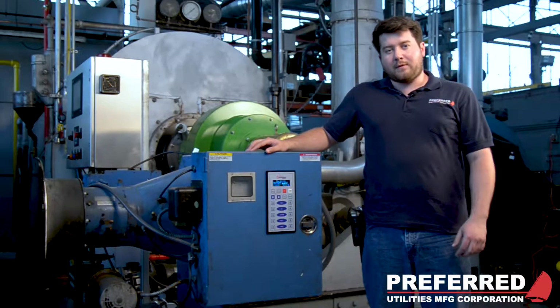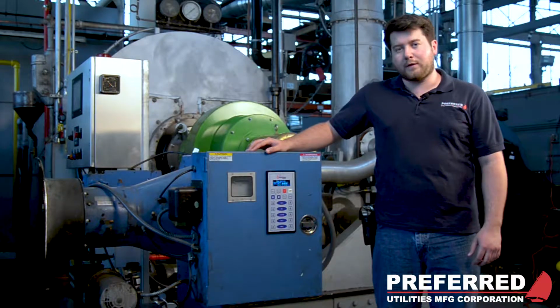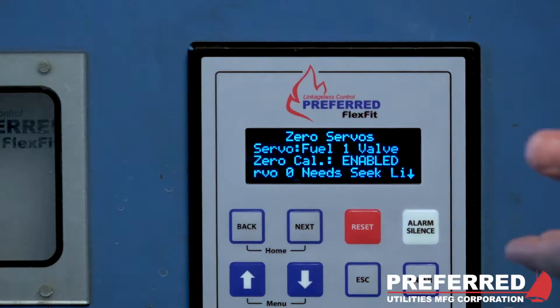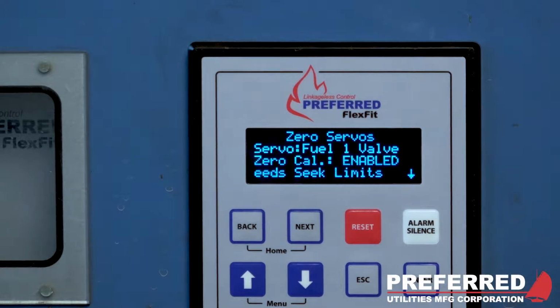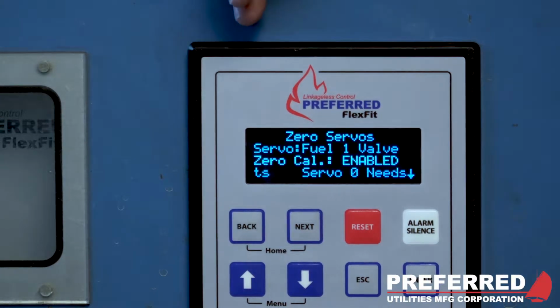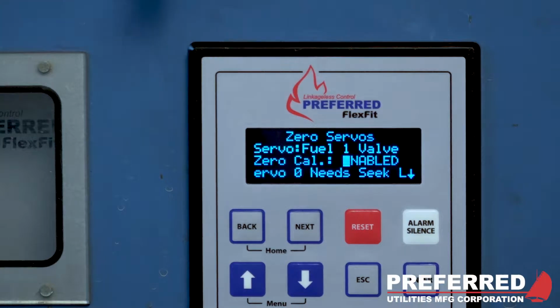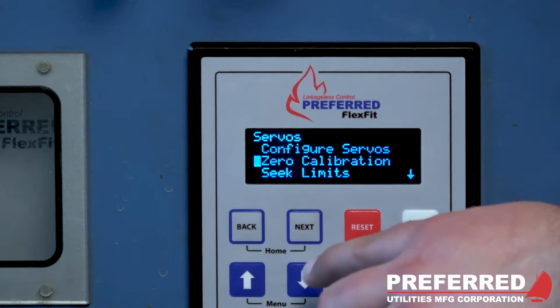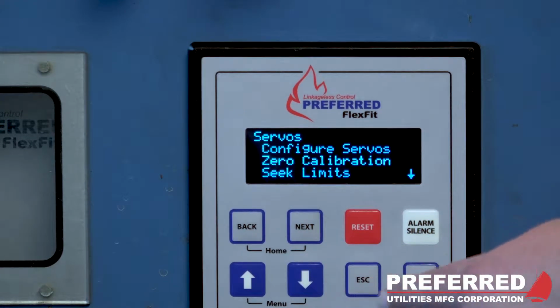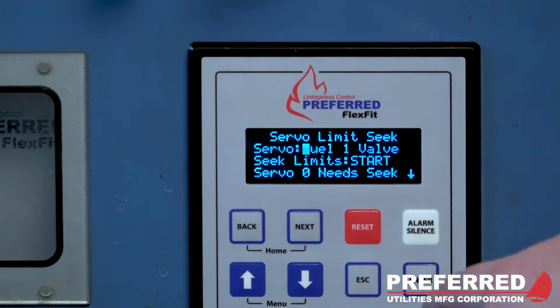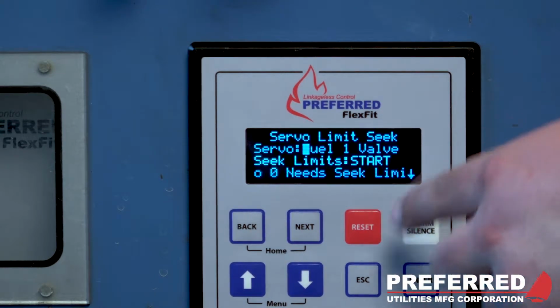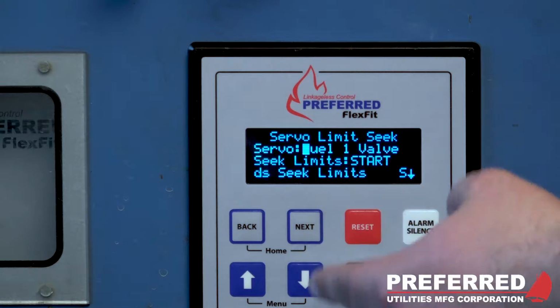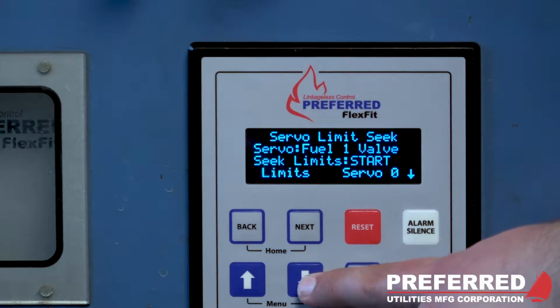Okay, now that we have established our 0% on the servo, you're now going to see an error message come up saying servo 0, or whichever address you are working on, needs seek limits. So we'll press escape, scroll down one time to seek limits, and make sure you're on the correct servo, which in this case is the fuel valve that we're using.